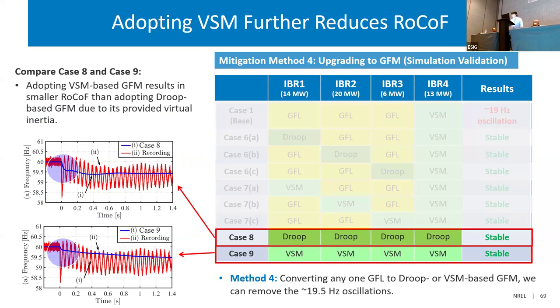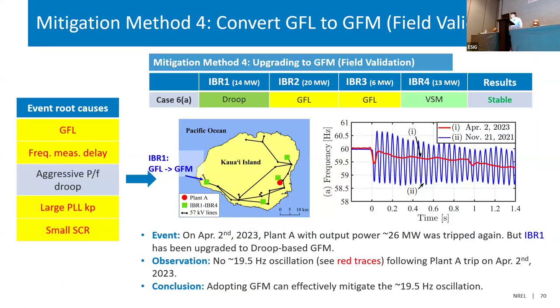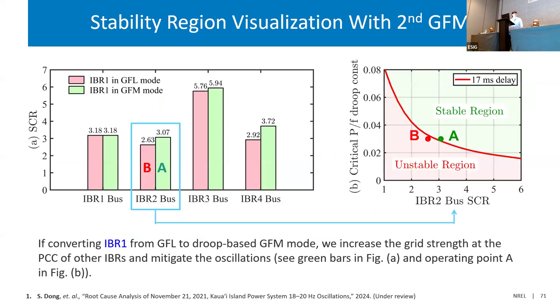For the comparison between droop and VSM: VSM provides virtual inertia, and we can see from the Nyquist curve comparison that using VSM generates a smaller Nyquist curve. These are all simulations — all models are wrong, but some are useful. So here is one field data validation. Since August 2022, Kauai actually converted one grid-following inverter — IBR-1, corresponding to case 6A in our study — into a grid-forming one. Later, on April 2nd, 2023, they experienced a very similar event with similar N-1 contingency. We get the red trace without any oscillation, compared to the blue trace from the previous simulation. In the field validation, it addressed the oscillation event.